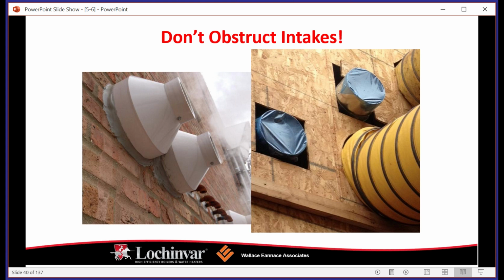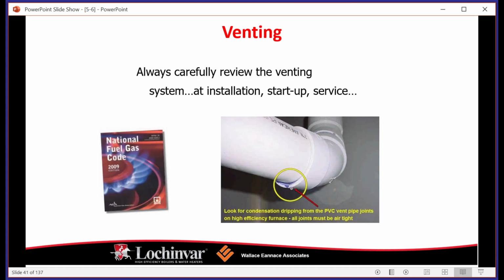I know all of us joining in have some exposure to the boiler industry, so I'm sure we are all kind of shaking our heads at some boneheaded thing we've seen done. So again, these are some particularly bad examples. But again, be aware, don't obstruct your intakes, don't obstruct your flues for certain, and make sure that you have significant enough clearances above snow, even stuff like landscaping mulch or anything like that. If you're too close to the deck, you do run the potential problem of pulling stuff in through your intake air, and all that stuff's going to get pulled into your equipment and it's not going to run efficiently.